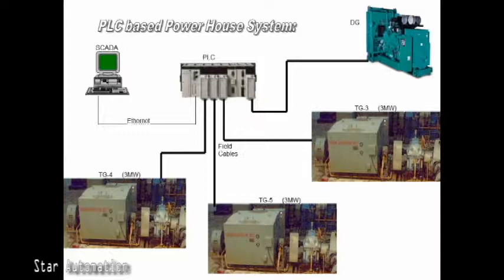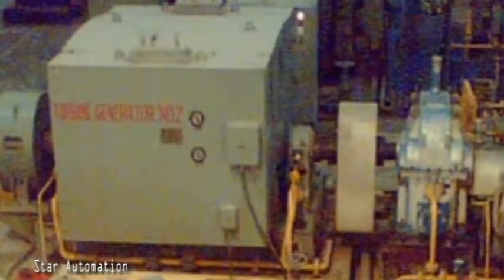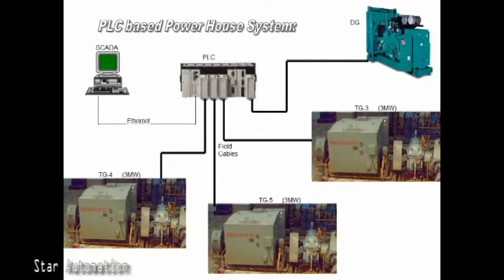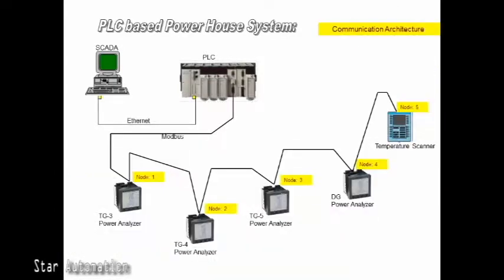In this project we have three TG sets of 3 MW each and one 1000 kVA DG set. A Programmable Logic Controller (PLC) was used to get various inputs and outputs from these power sources and associated circuit breakers and bus couplers. The PLC was used for auto synchronization of TG sets and auto load management. SCADA software communicates with the PLC over Ethernet to display real-time parameters and allow the operator to control the powerhouse from one place.